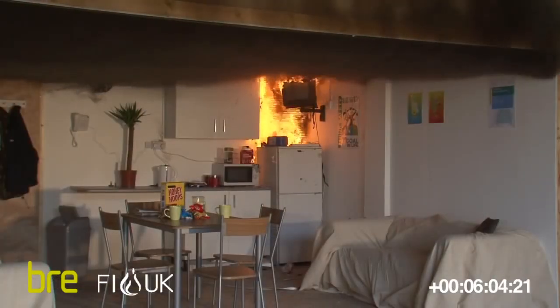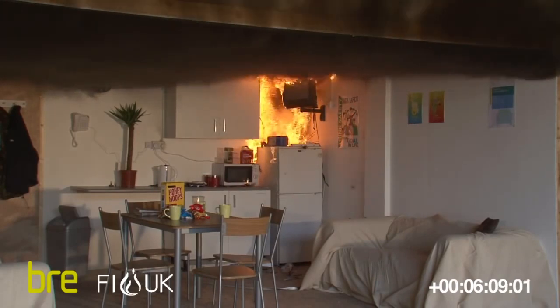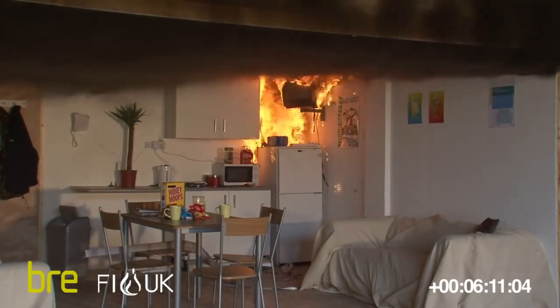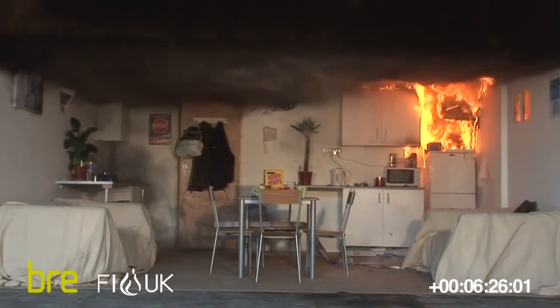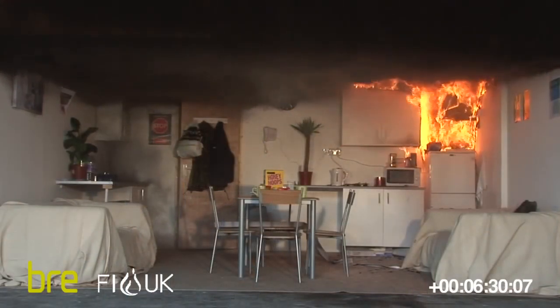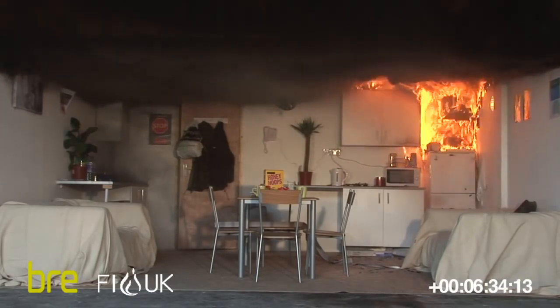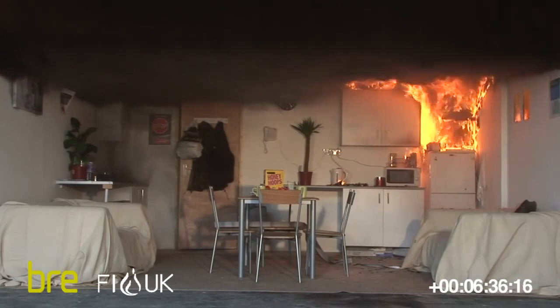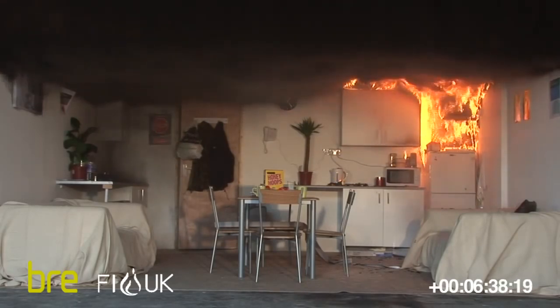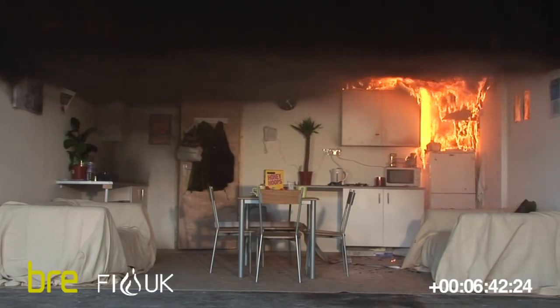Some of you may be starting to feel the heat already coming off this. That's the light fixture that's come off the ceiling. And again, the energy of the fire is continuing to increase, the velocity of the smoke that's coming out of the room is continuing to increase. And at this point, the hot smoke layer is re-radiating quite a lot of heat back down onto the fire and indeed everything else in the room. So it's accelerating the growth of the fire and heating up the surfaces of all of the contents within the room.